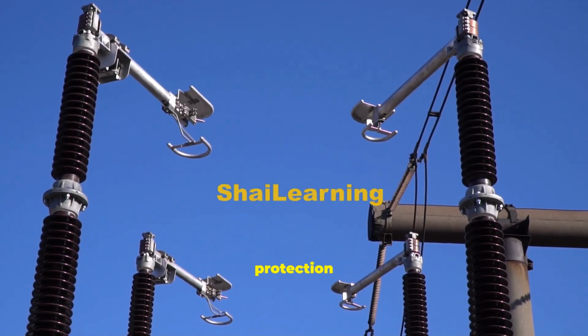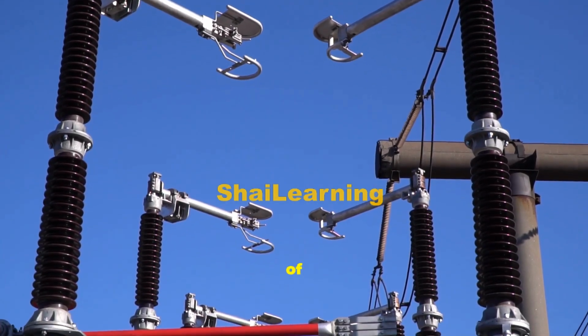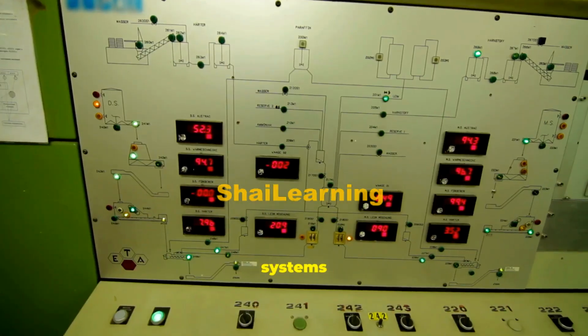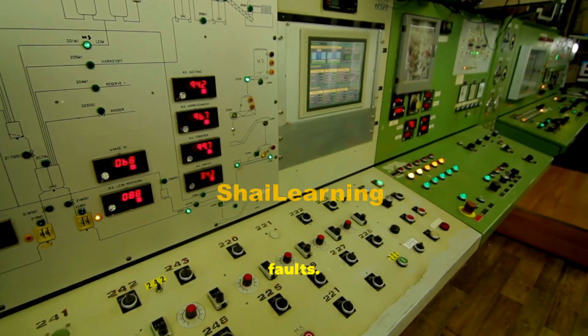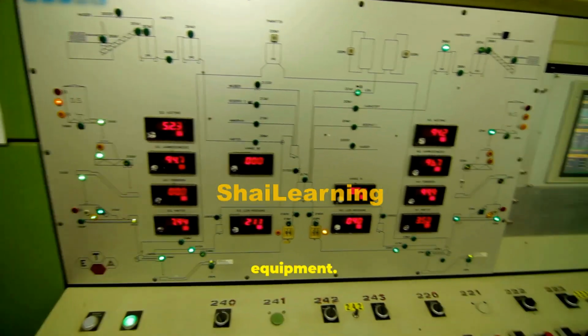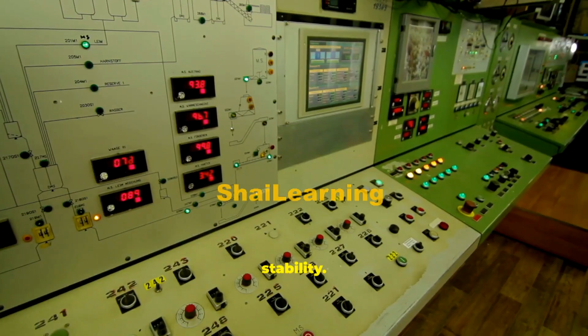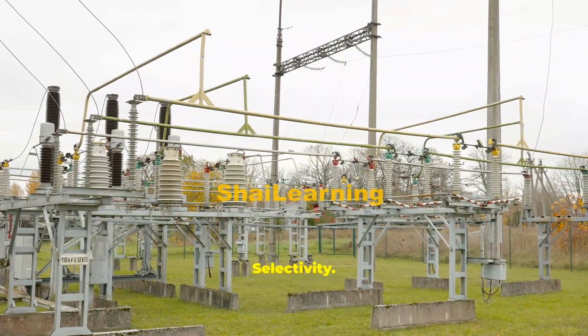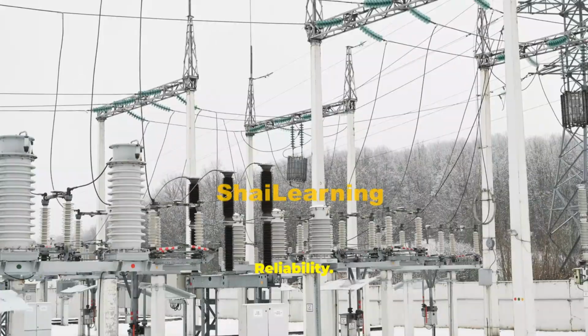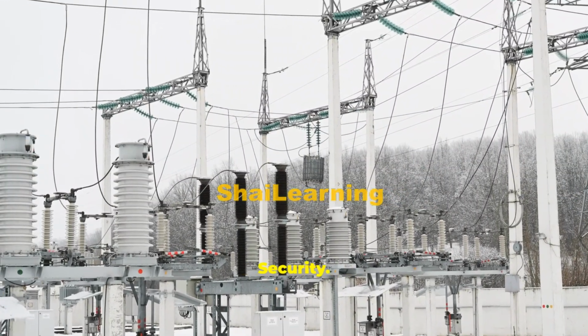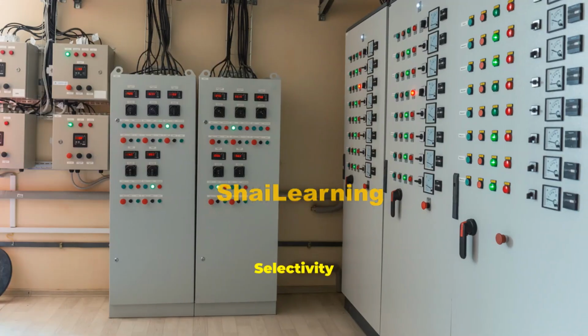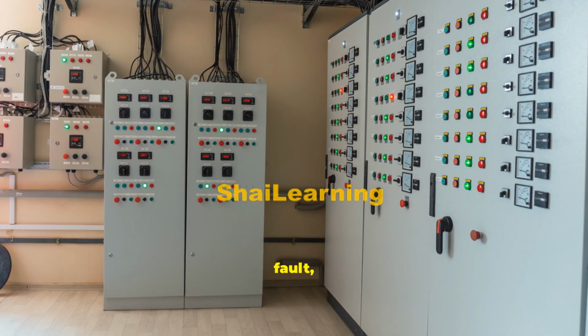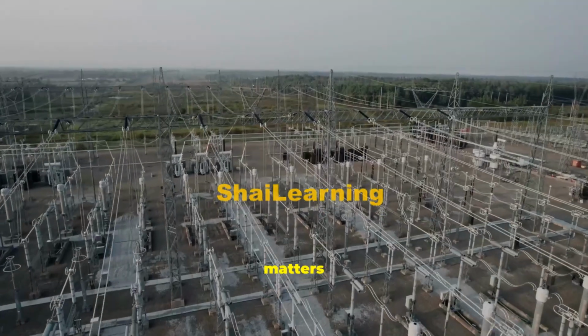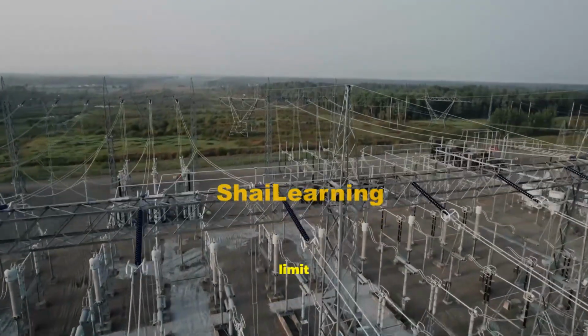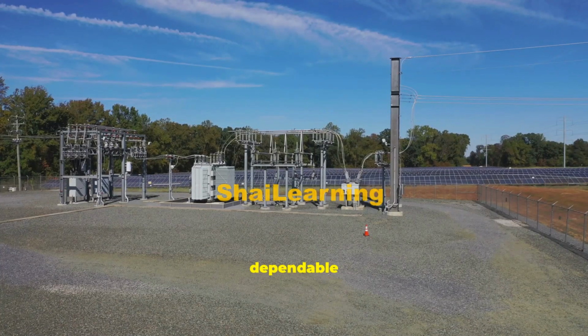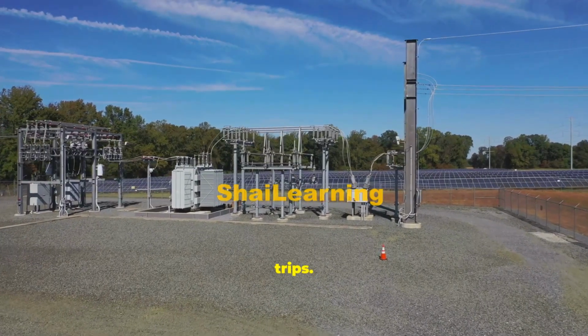This is the job of the protection and control system, the brain and nervous system of the substation. Protection systems exist to do 3 things: detect faults, isolate faulty equipment, maintain system stability. Key principles include selectivity, speed, reliability, dependability, security, stability. Selectivity trips only the breaker closest to the fault, keeping the rest in service. Speed matters. Relays operate in milliseconds to limit damage. Reliability means dependable operation and security against false trips.